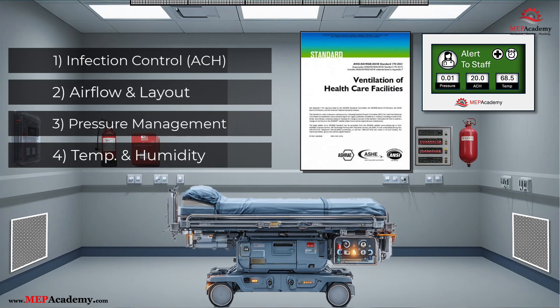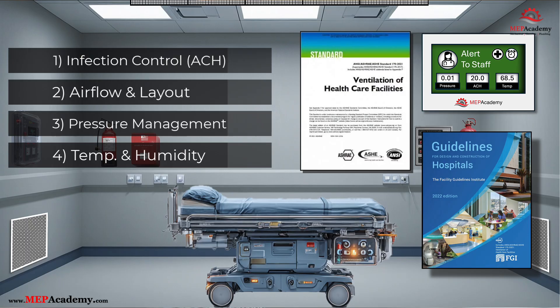4. Temperature and humidity control: Maintaining precise temperature between 68 to 75°F (20 to 24°C) and humidity between 20 to 60% RH in hospital operating rooms is critical for patient safety, staff comfort, and infection control. These conditions, mandated by ASHRAE 170-2021 and FGI guidelines, prevent microbial growth, reduce static electricity risks, and ensure optimal surgical outcomes. Building management systems (BMS) with thermostats and hygrometers enable tight control using reheat coils, humidifiers, and dehumidifiers to maintain stability, even in variable air volume systems during setback modes. This underscores the balance between environmental precision and energy efficiency in OR HVAC design.